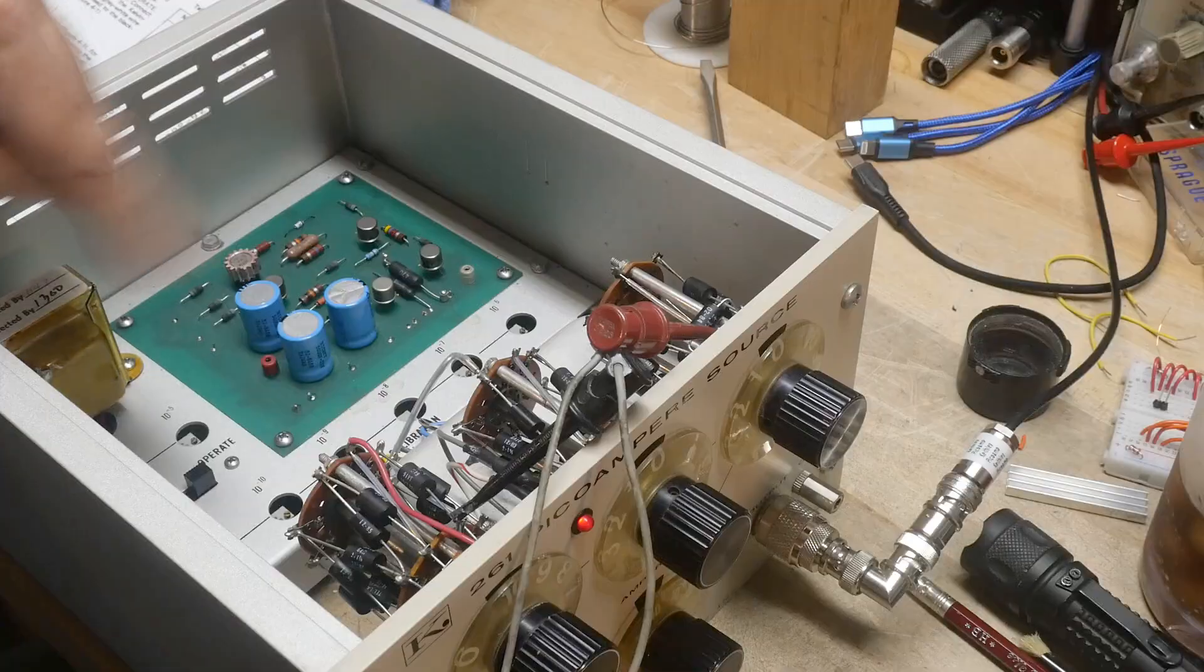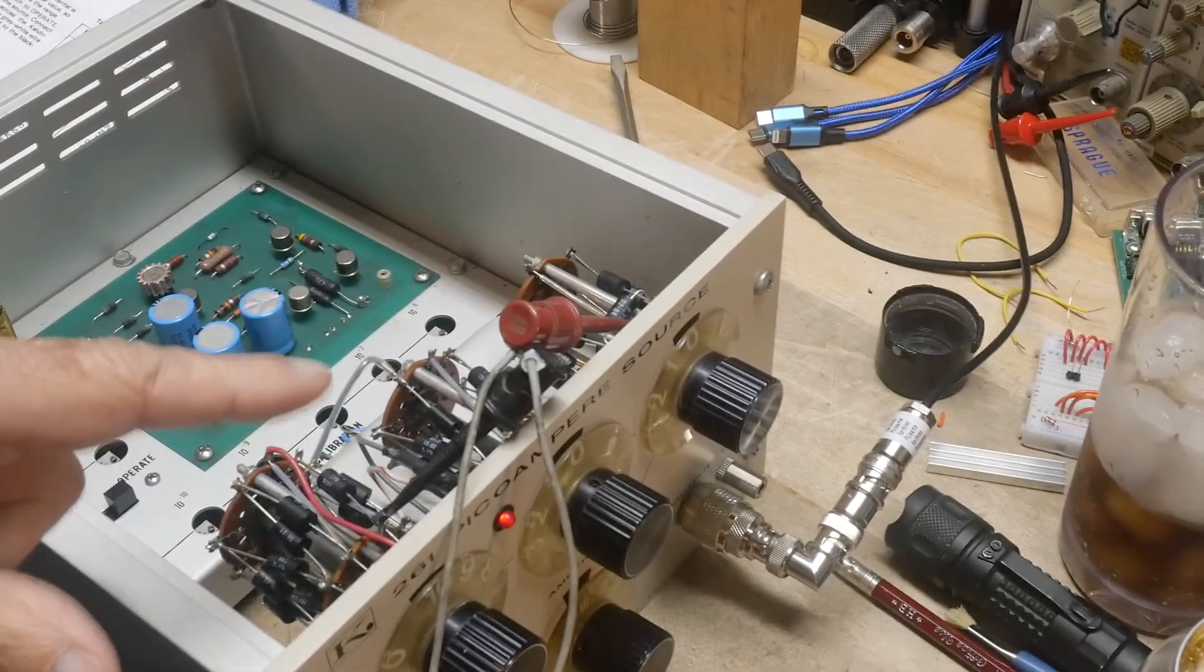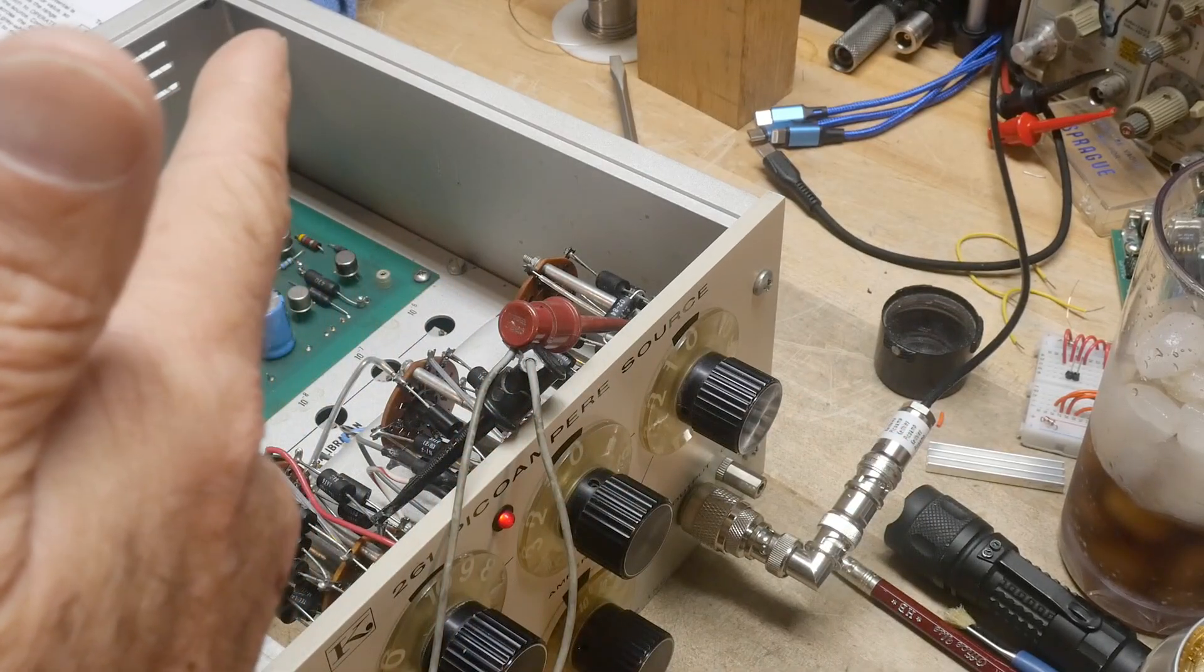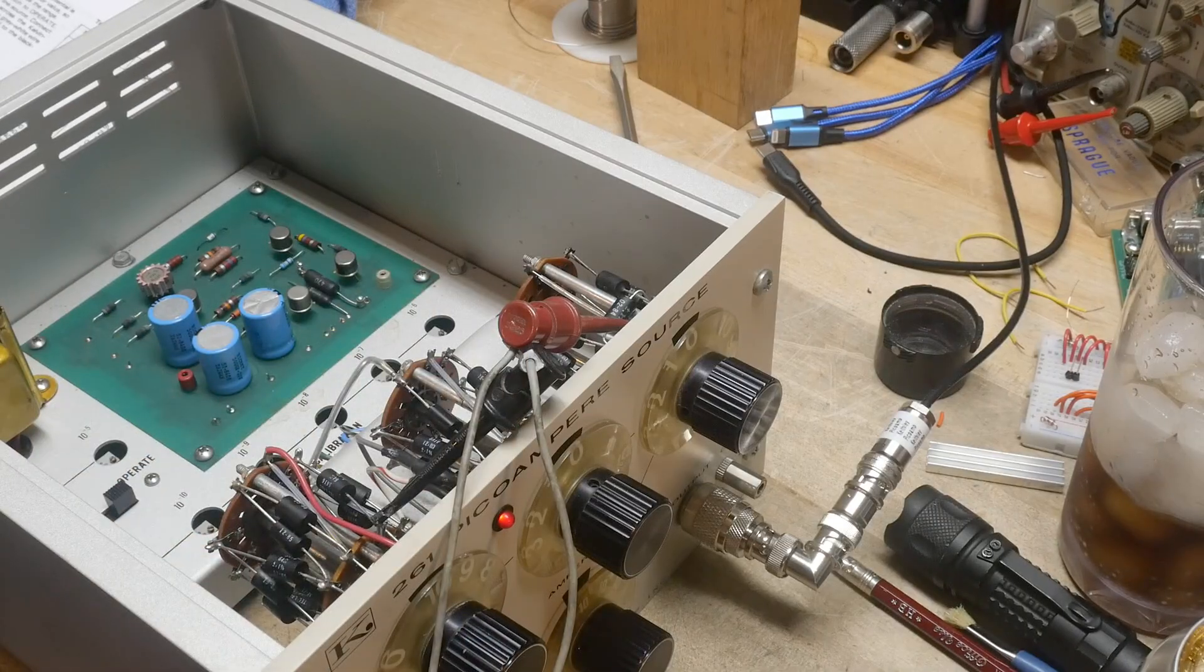All right, the way that you do the calibration is you adjust these potentiometers for minus five, minus six, minus all the way to minus twelve - there's one for each range, and you're monitoring the voltage. They said that the voltage divided by the resistance is the current, and all the resistors are accurate, so you set the voltage to match the resistors.